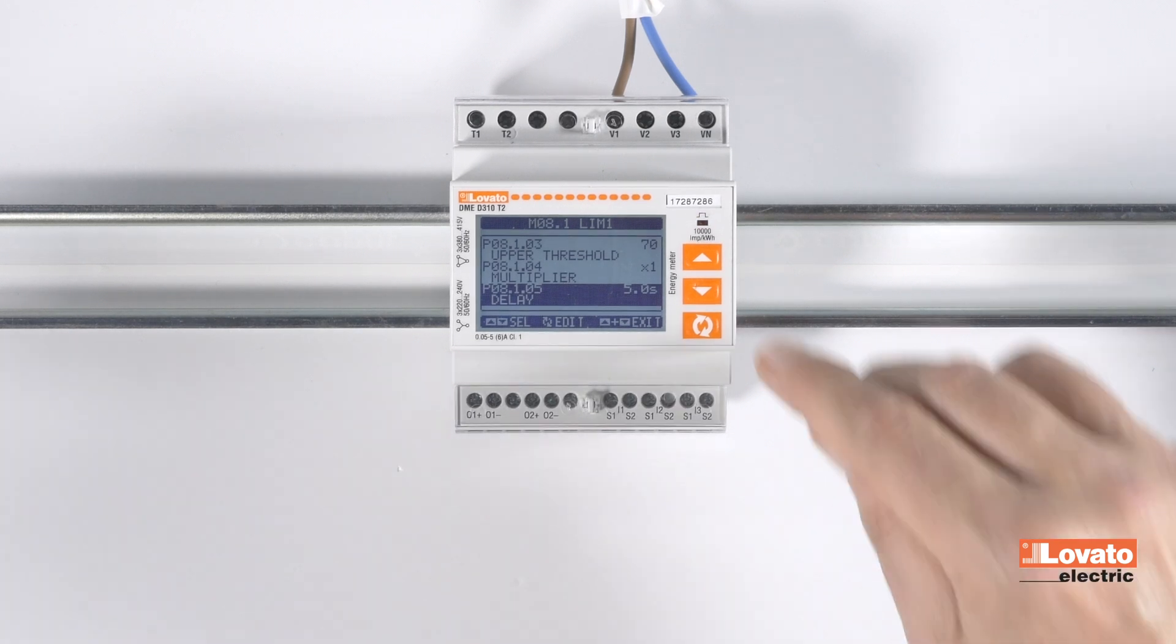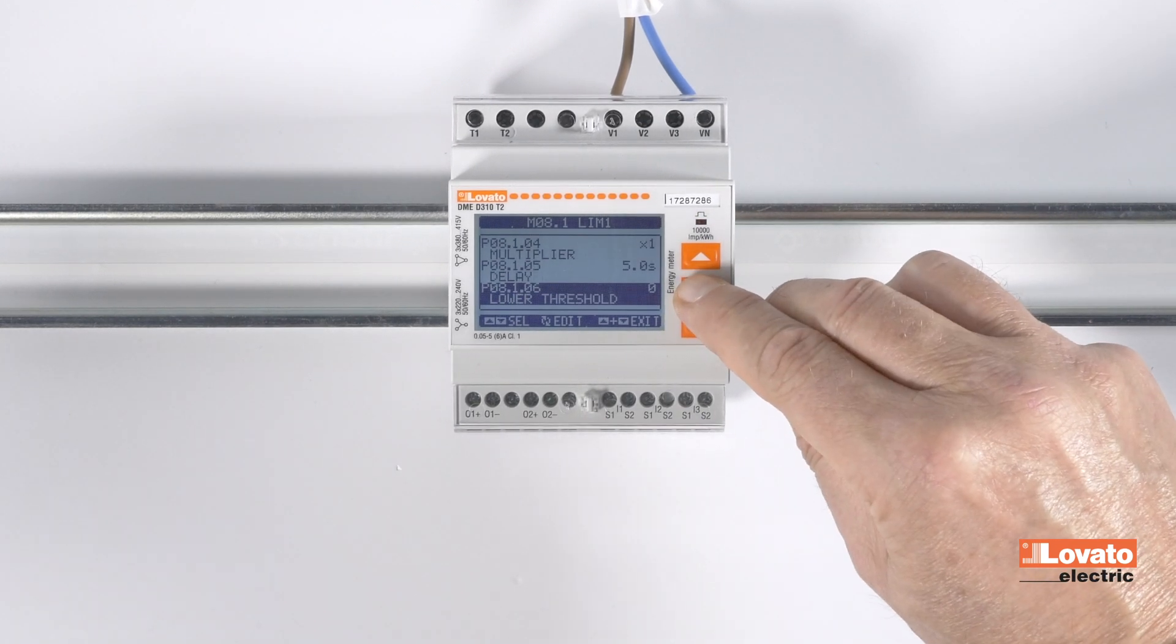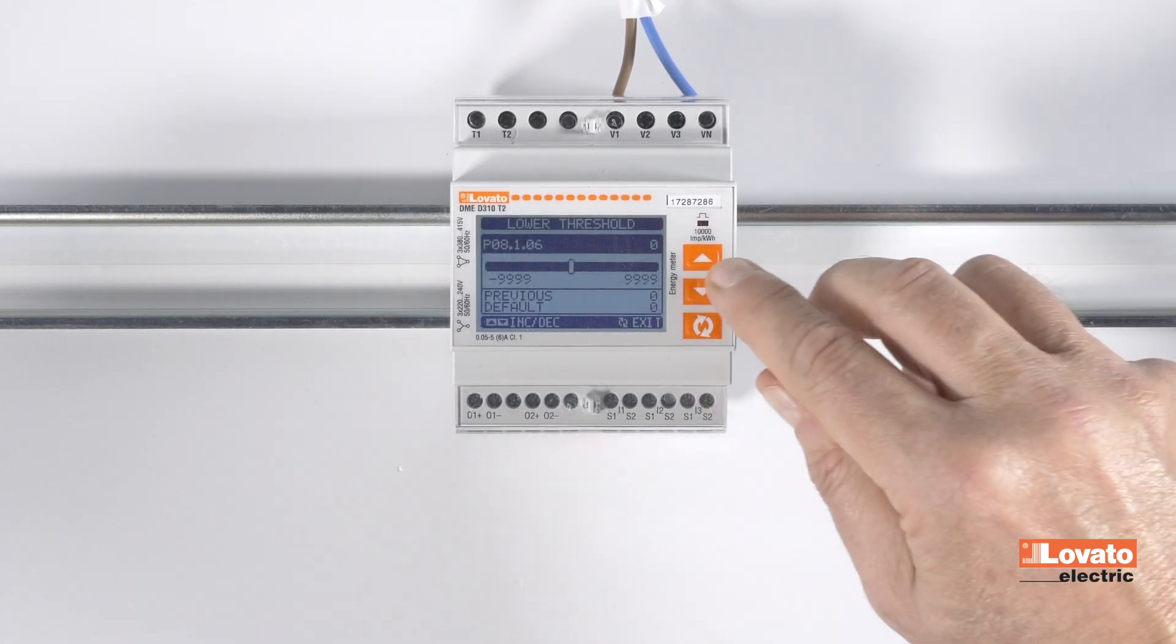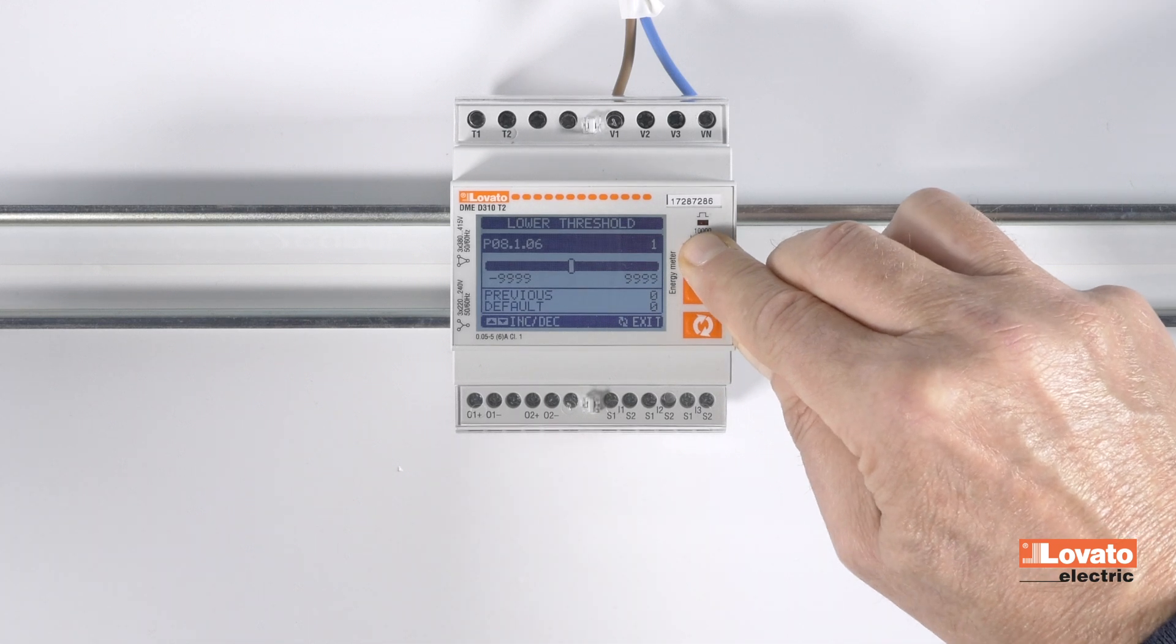Now, we'll set the reentry threshold. Select the item Lower Threshold and enter the value, 50 amps for this example, and confirm.